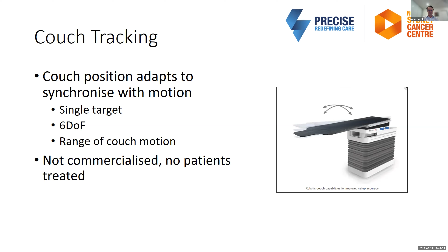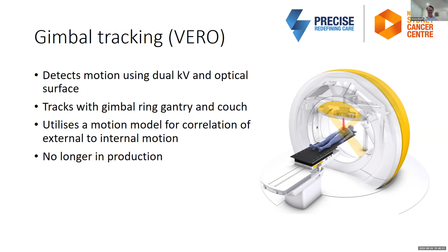The Vero system used a gimbaled tracking system. It also had dual kV X-ray systems and an optical surface scanner. It tracked with the gimbal ring gantry. So the gantry itself sort of pivots, if you like, forwards and backwards to realign the beam. If you look very closely in that image, you can see that the beam is moving superior and inferior based on the gimbal of the linear accelerator. It also uses a motion model for correlation between the external and internal motion. This was a fantastic system, but unfortunately is no longer in production.